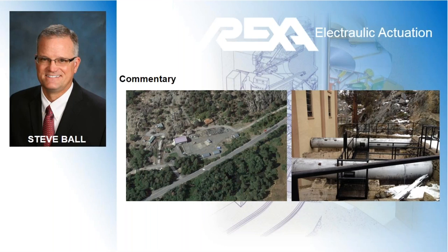So the second unit is the one we're going to look at here, because that's the one that was converted to use a REXA product for actuating its power needle. Unit 2 we have rated as 6 megawatts. It has a maximum flow rate of 50 CFS at the needle. That's again at full head or full reservoir and that sort of thing. So that's a maximum possible.